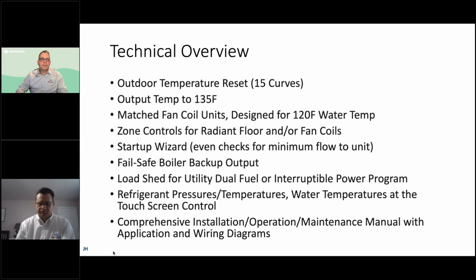Next slide, please. The outdoor temperature reset is a huge savings in operating costs. There are 15 curves. So based on the outdoor temperature, we can change the minimum and the maximum load temperatures. In other words, the temperature being supplied to the hydronic zones and heating, so that we can operate at the lowest temperature possible for the highest COP. When it's very cold outside, it will max out at the design set point, or when it's in hot water mode, it can go up to 135 degrees Fahrenheit to heat that hot water tank.